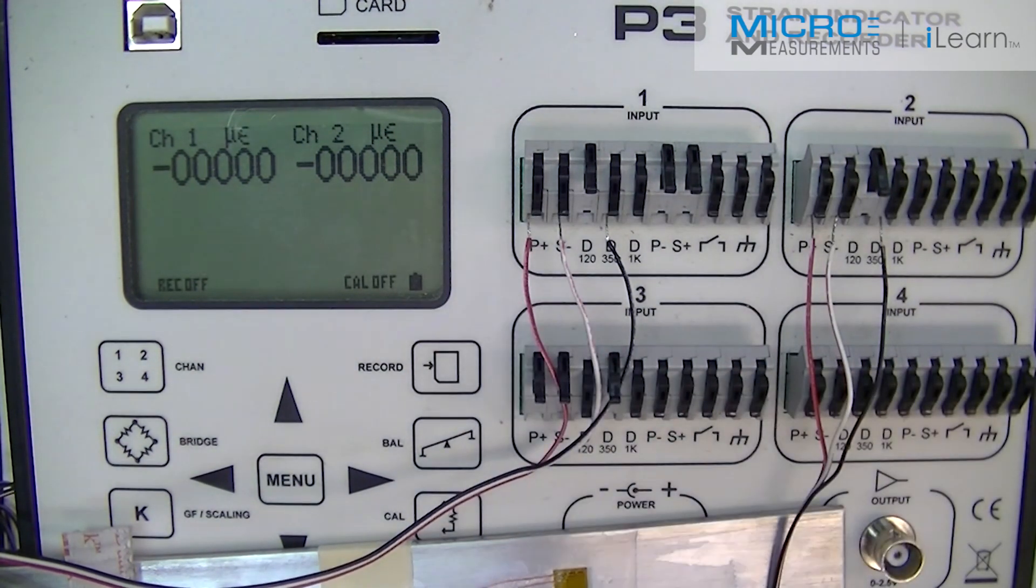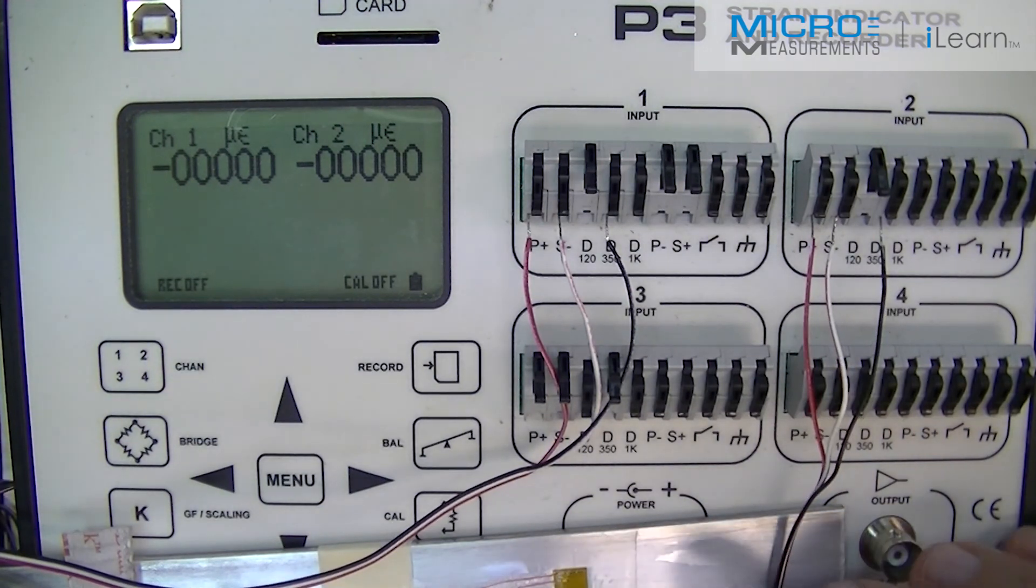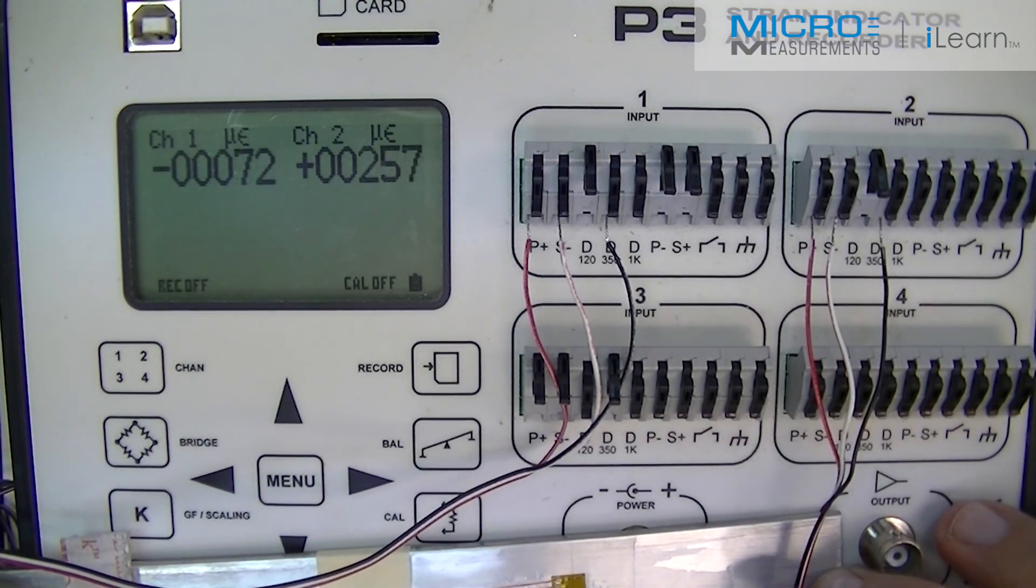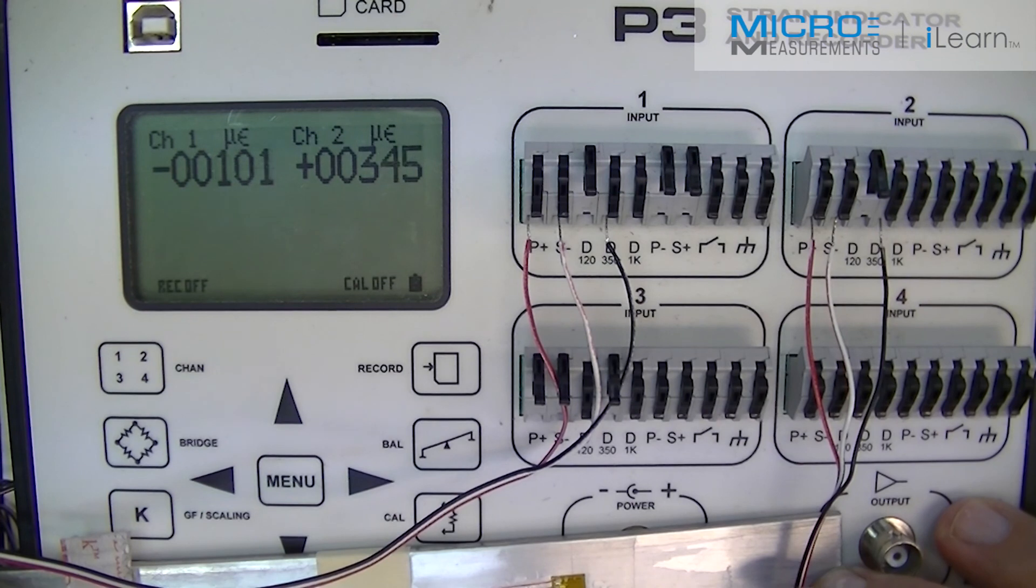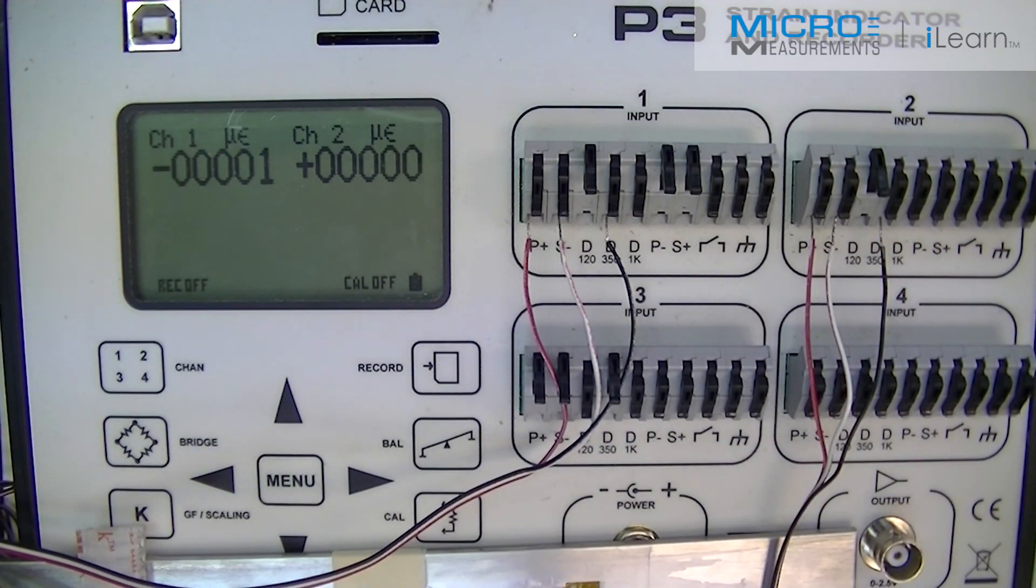If I can apply a load to this beam, you can see several hundred microstrain, especially on the linear gauge, and then release that load, it should return to zero as it does. That is your best indication that the strain gauge is functioning correctly, and that your installation is well bonded.